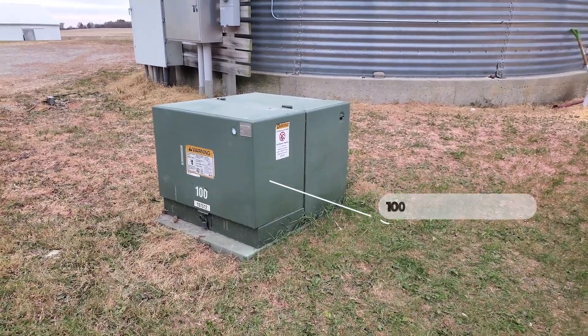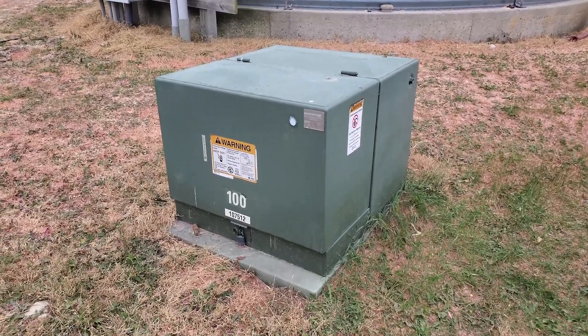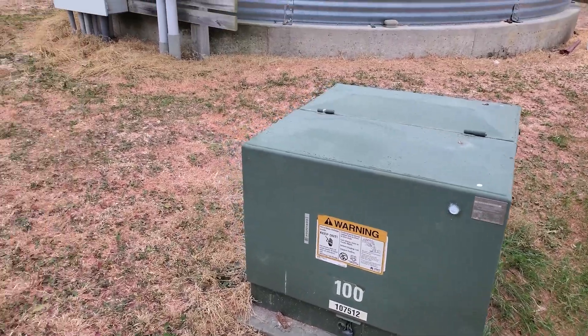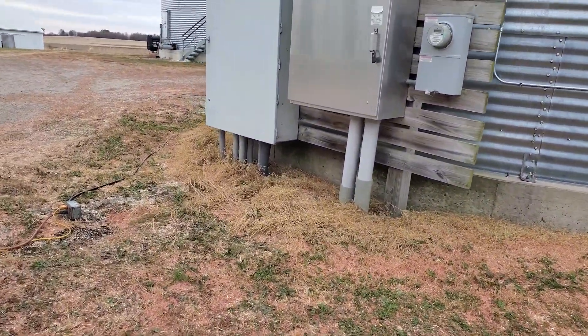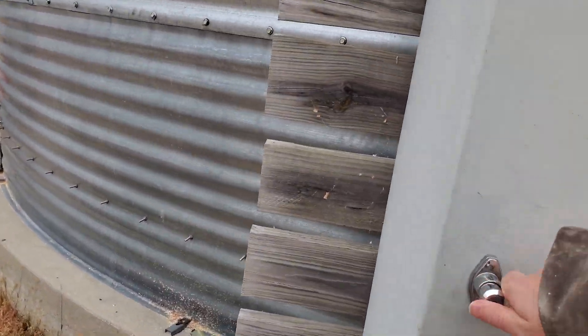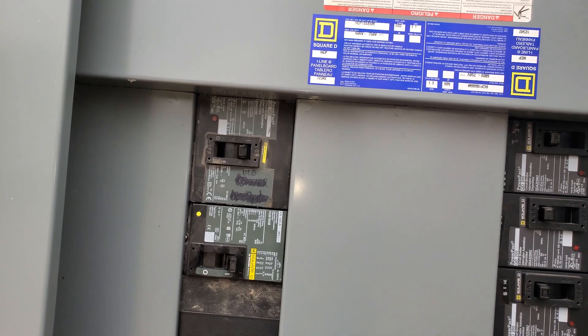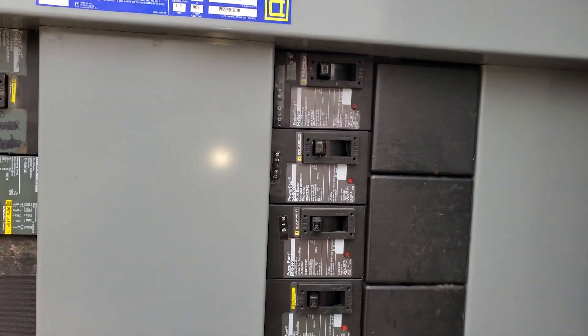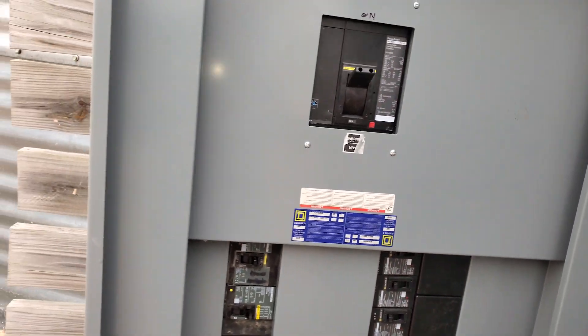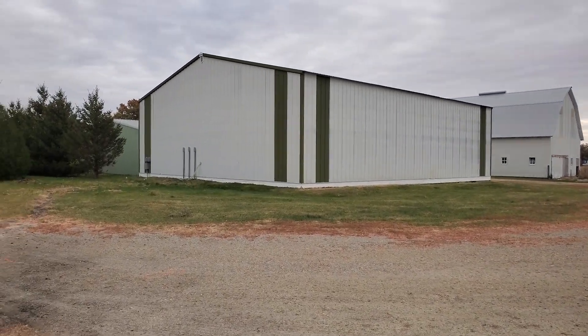So this is our 100 kVA transformer. Well, it's not actually ours — it's the power company's. It's 100 kVA, 120/240. So just a normal residential type of transformer. And it can run 600 amps through it. And here is our 600 amp main panel. This is obviously our 600 amp main breaker. And all these other breakers are about 200 amps — they're for the drying system we have for the grain bin site that we're on. These three bottom 200 amp breakers are for our mining setup. And obviously those wires are run underground through the side of the shed through there.